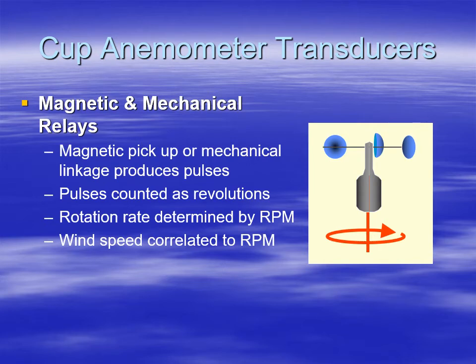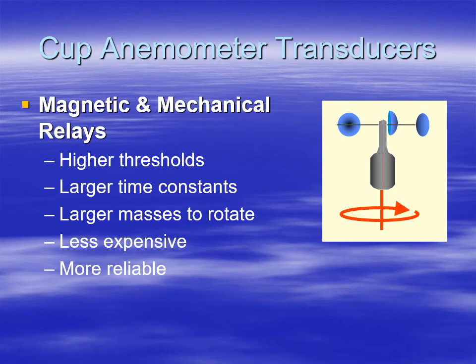Magnetic or mechanical relays as a transducer. This is where you have a magnet attached to the shaft. As the shaft rotates, there is a device, whether it be a Hall type device or something else, that actually measures the rotation as the magnet passes by. And because of that, you can count the number of rotations of the cup over some given period of time. In other words, revolutions per minute. And based on that, you can calibrate the revolutions per minute to a wind speed. Now, once again, you have either a magnet or some sort of device attached to the shaft, so it's more massive. More massive means that you have larger distance constants, higher threshold wind speeds, but these are less expensive and they are more reliable.